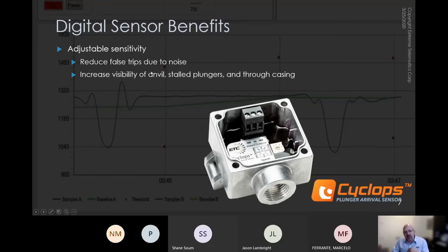As well, if you're dealing with non-ferrous plungers, like a titanium or aluminum plunger, or plungers that just don't have a lot of ferrous material, you can put the sensor up on the lubricator at the anvil and increase the sensitivity so you can see it there. Or you can put it lower and turn up the sensitivity to see it before it arrives. You can see through casing or machined solid lubricators. So there are lots of ways to adjust the sensitivity for the circumstance in which you're deploying the sensor.